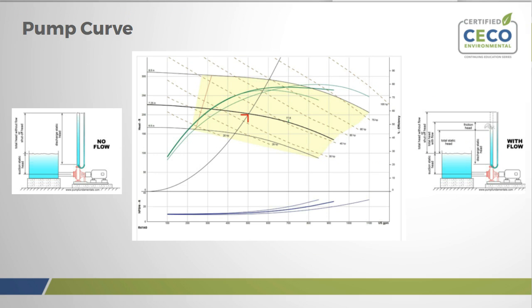Centrifugal pumps are basically defined by a pump curve. Unlike a positive displacement pump, which will basically put out the same amount of flow regardless of the amount of energy you put in, the centrifugal pump works as a velocity machine, if you will. The flow rate that will be produced is dictated by the amount of system pressure that it is pumping into. So the flow rate changes with the amount of system pressure, back pressure on the system.